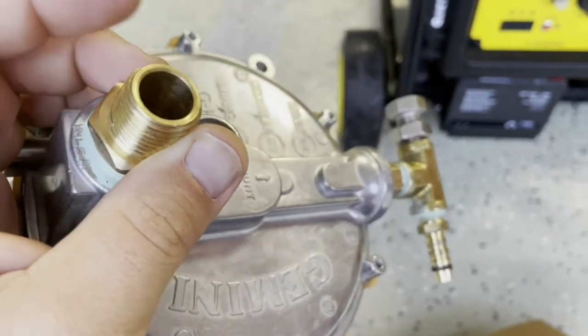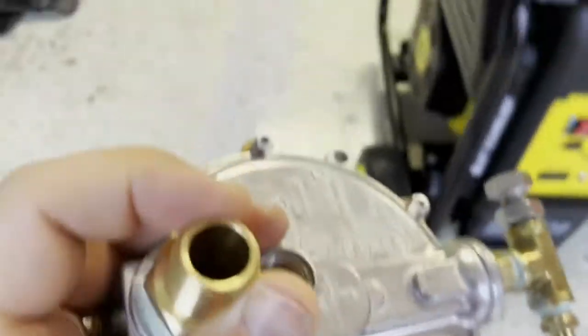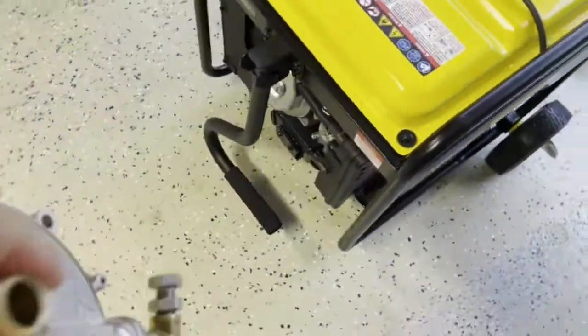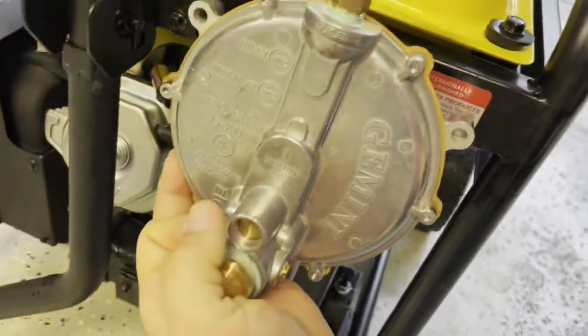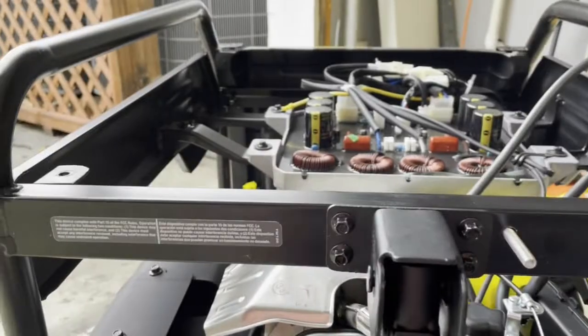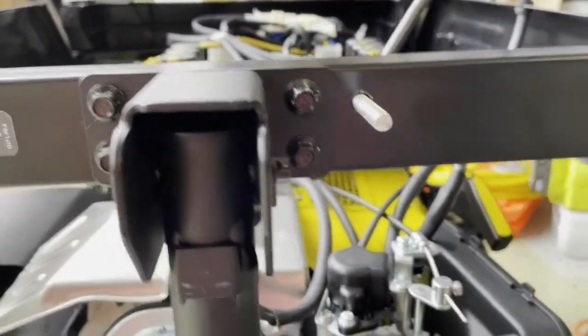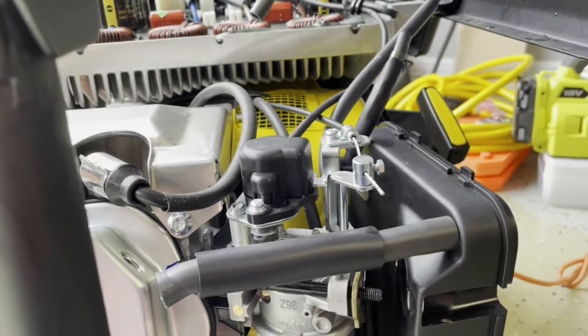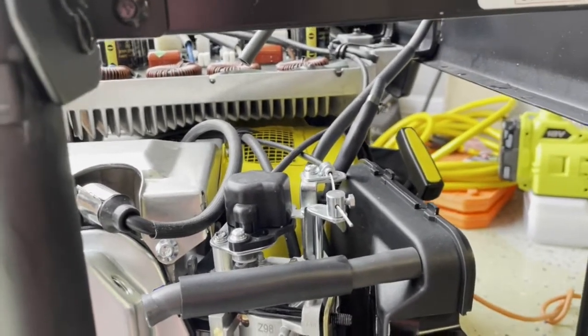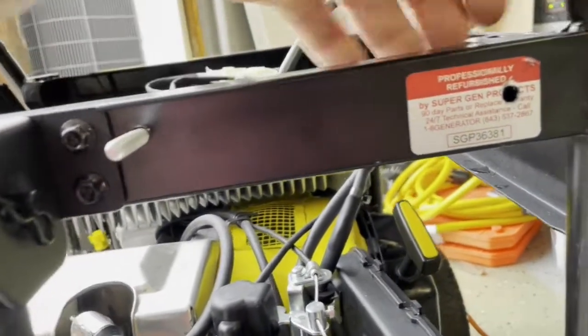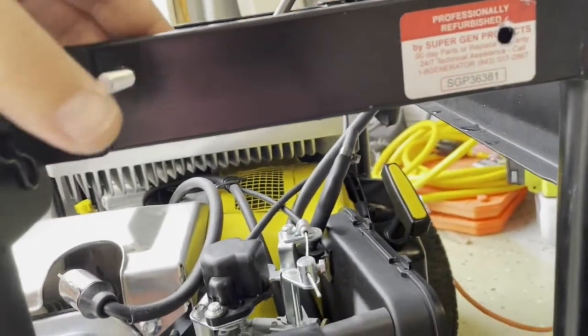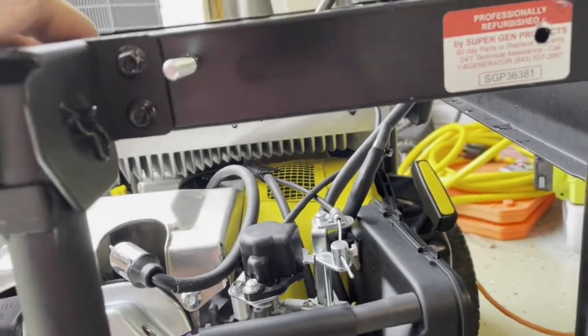I will put a shut-off valve here and install it right by the frame, drilling through the frame so the gas can go to the carburetor from this point. Here's what I'm doing: I removed the gas tank, which has 4 screws. You need to unplug the carburetor, shut off the gasoline valve, and drain the line by running the generator a few minutes, so I can easily drill these 2 holes without damaging the gas tank.